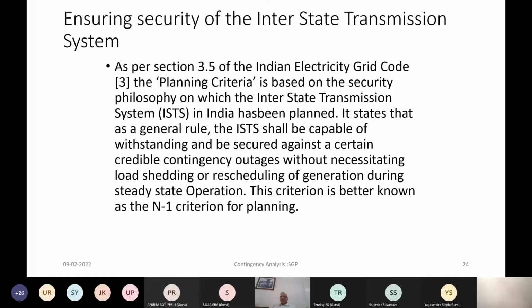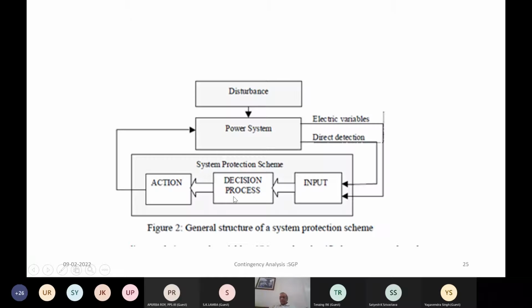This is again a clause from the grid code. It says the planning criteria is based on the security philosophy on which the interstate transmission system in India has been planned. It states that as a general rule, the ISTS shall be capable of withstanding and be secured against certain credible contingency outages without necessitating load shedding or rescheduling of generation during steady state operation. This criteria is basically known as N-1 criteria. So this is a provision in the grid code and technical standard.